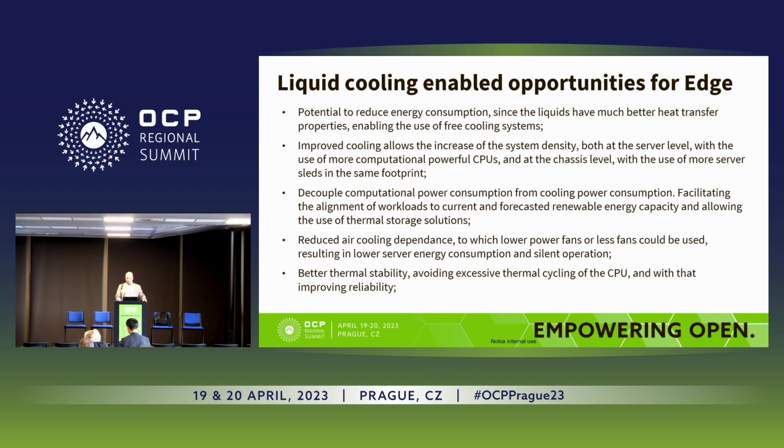And then of course with lesser fans we can reduce acoustic noise and lower server power consumption. And then one finding is that there is better thermal stability, so no that kind of fast transients in thermal temperature of CPU, and of course this can increase reliability of CPU.